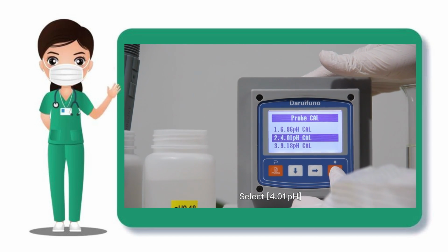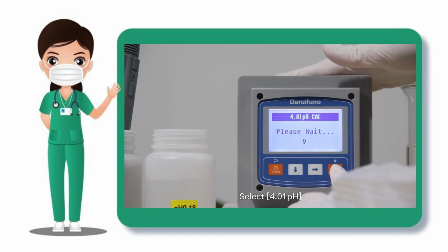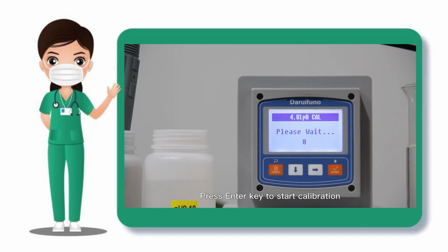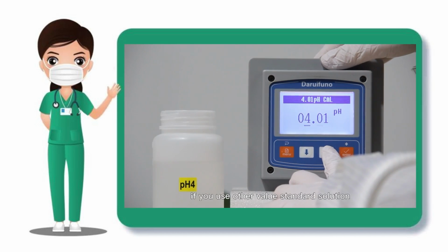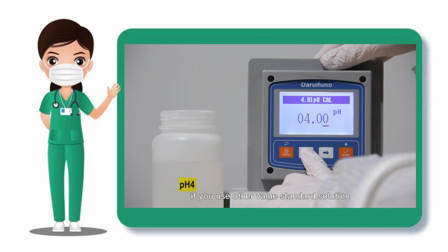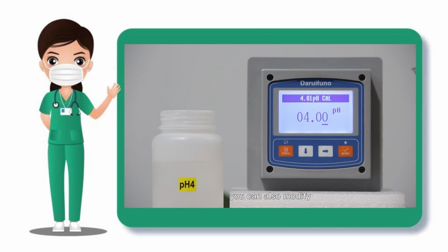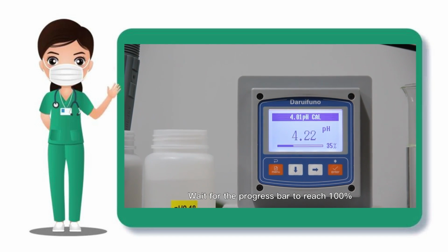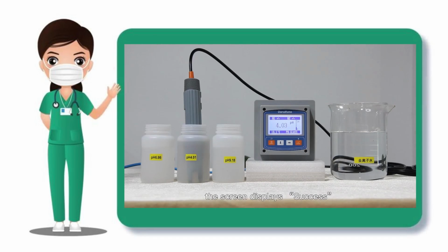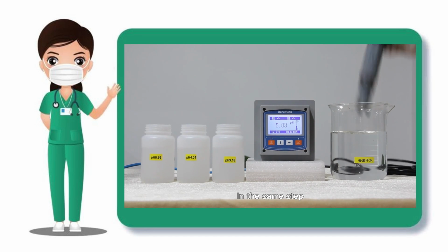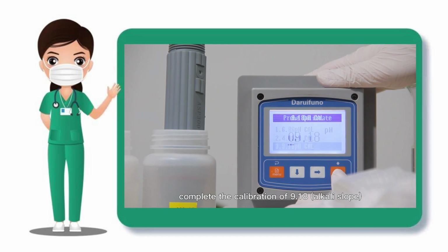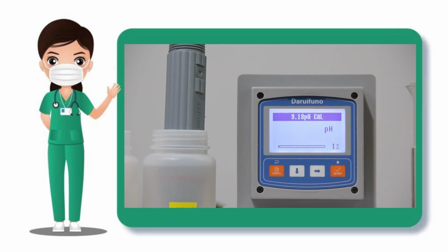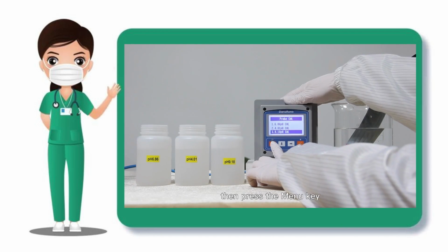Select 4.01 pH. Press the enter key to start calibration. Similarly, if you use a standard solution of another value, you can also modify it. Wait for the progress bar to reach 100%. The screen displays success. The calibration of slope 1 is completed. In the same steps, complete the calibration of 9.18. Then press the menu key and return to the main interface.